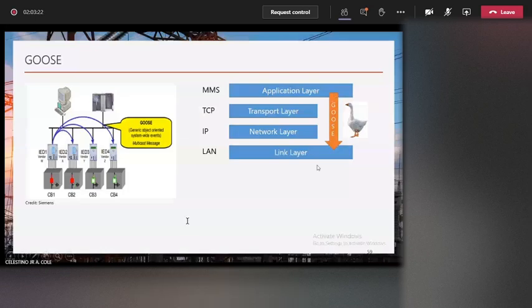So in the system, or in IEC 61850, the requirement is 4 milliseconds. Without the GOOSE message, this 4 millisecond requirement cannot be materialized. That's why it's very important.